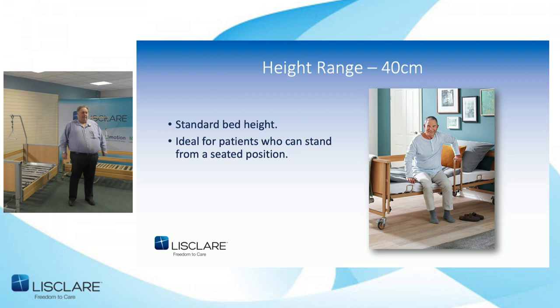The lowest entry and exit height of 40 centimetres for the user is the one that caused some issues. A short person would find it very difficult at that height to get in and out of the bed, especially with some of the very deep medical mattresses. So really, the height stated in the standards means that height range should be incorporated into the manufacture of the bed.